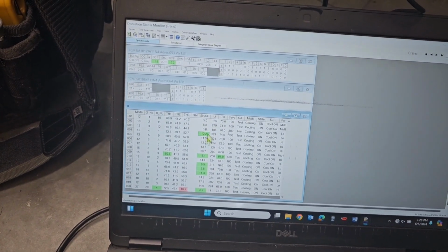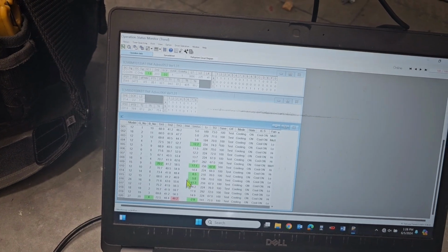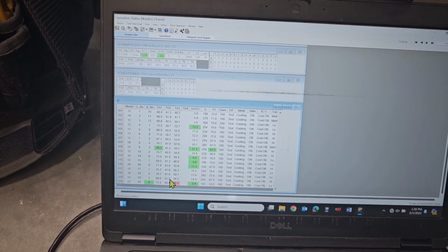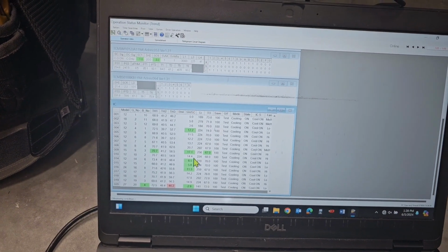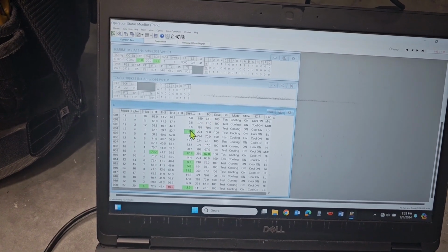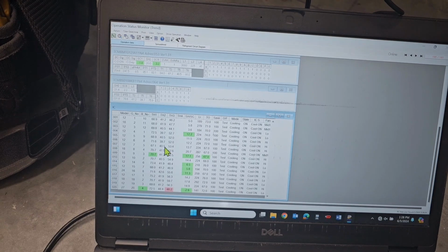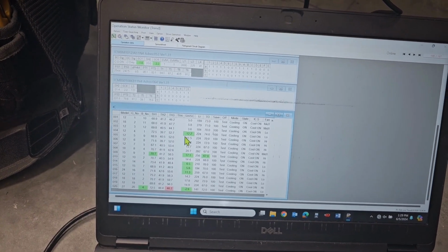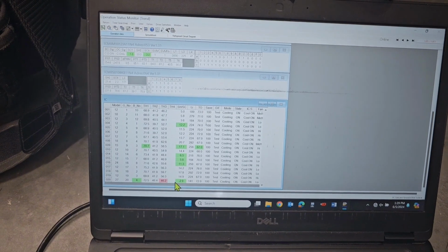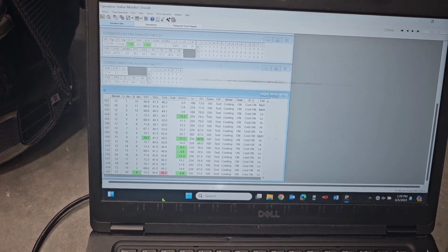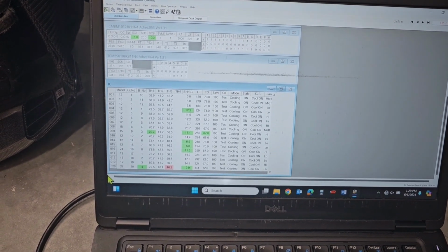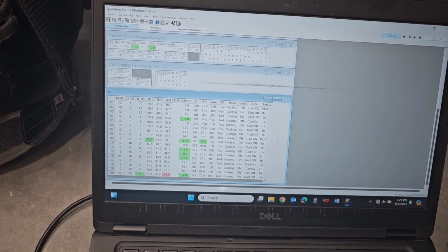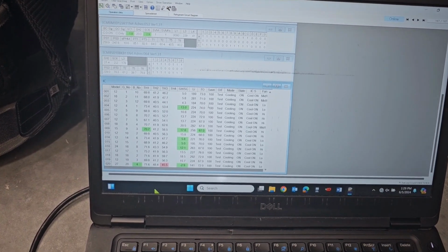If I close that and then all of a sudden everything goes back down to 2 to 5 degrees of superheat, then we know we have another problem and we're just chasing our tail. But if I close that valve and everything still looks the same, and then I can open that valve back up and then go close this valve again, and if everything comes back down to 2 to 5, then I can pretty confidently say there's not much more troubleshooting I can do to verify that that valve is flooding.